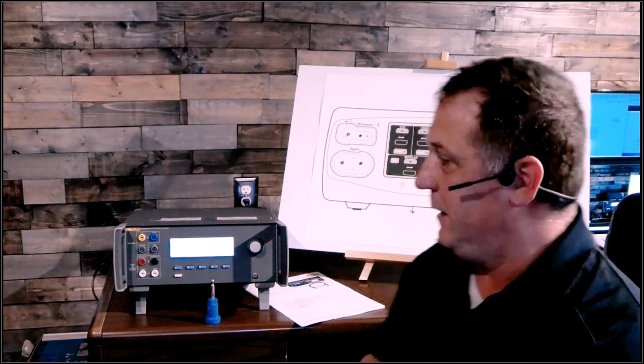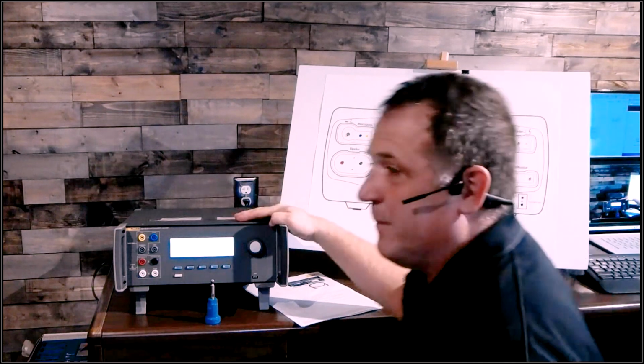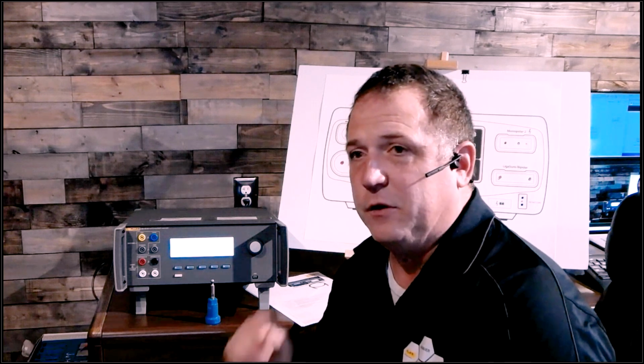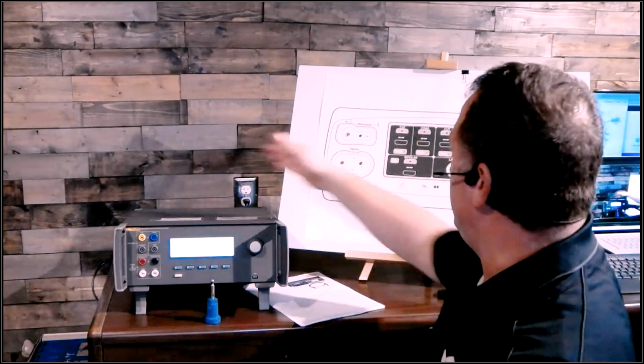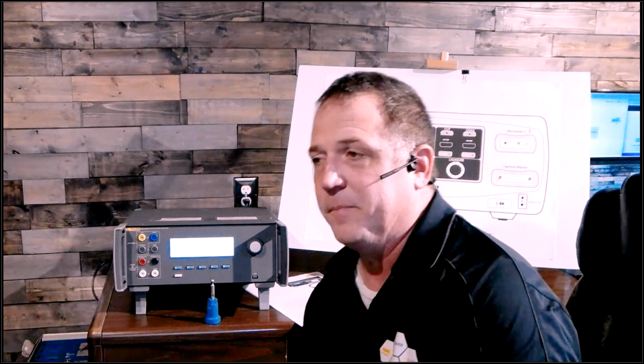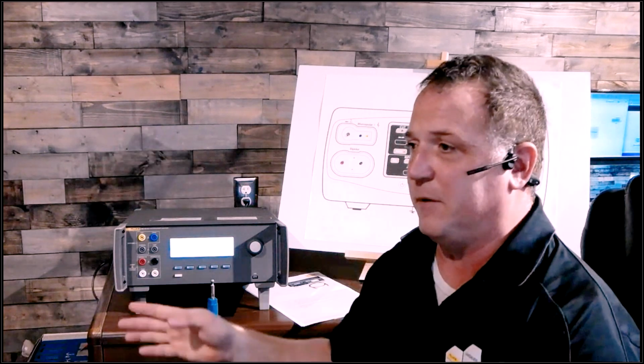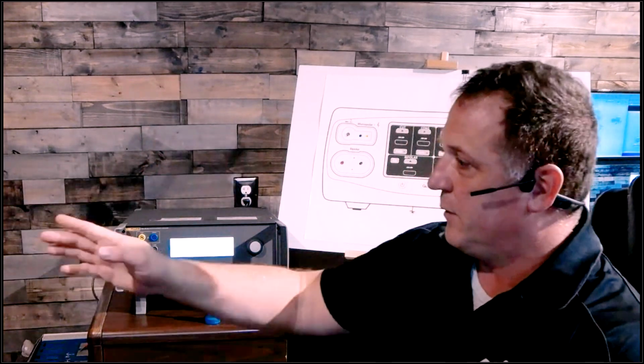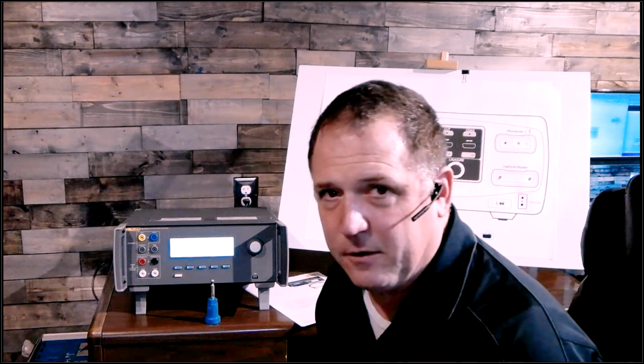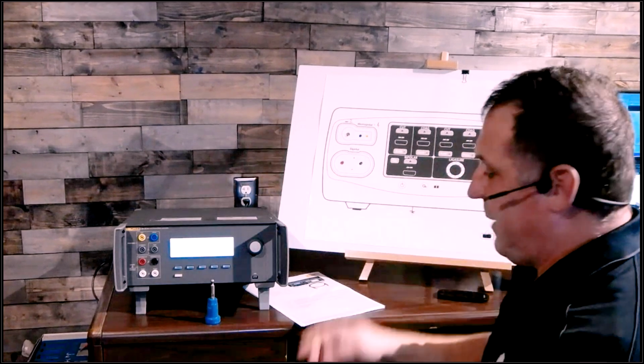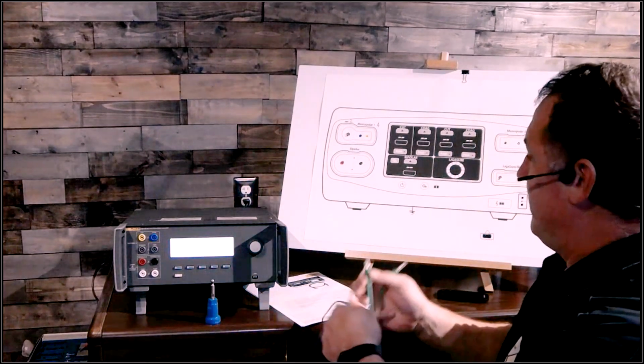More importantly on this, we're not stacked. And if possible, you do not want to be on a stainless steel back table, especially having the two units on the same stainless steel back table. You might want to have them on two separate tables, so you're not transmitting from one through the table into the other device. So try to have them separated, and don't add length.